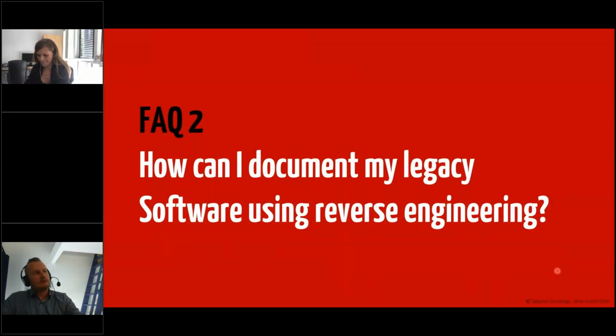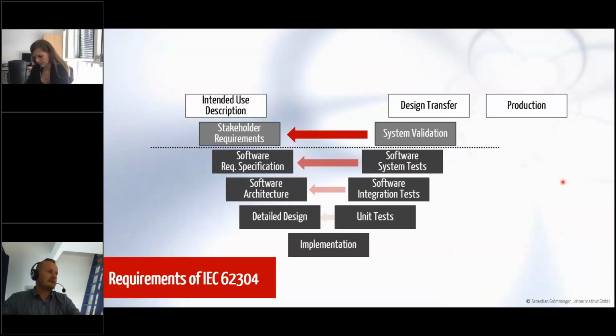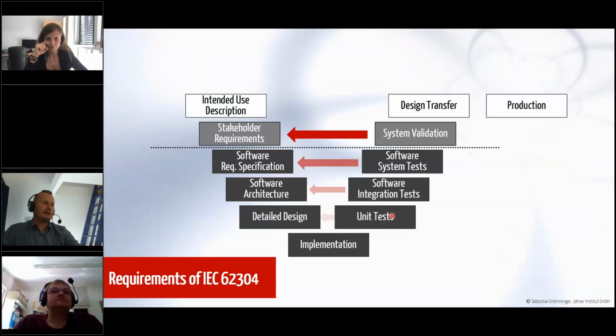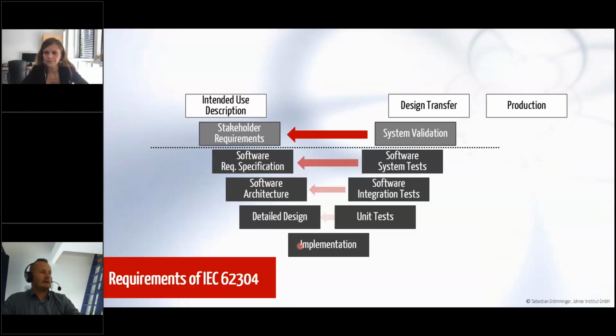The next question was, how can I document legacy software using reverse engineering? In this case, I would use the requirements of the IEC 62304 and the respective V model, and go from your system validation that you have hopefully done for your product already, and from that derive your stakeholder requirements. Hopefully you have done software system tests, and from those system tests you can derive software requirement specifications back. Most software systems will end up there because you won't find integration tests and unit tests. If you find those, you will certainly already have sort of a compliance to IEC 62304. However, if you're there, you can go this way in the normal way. So this would then not be, again, reverse engineering; you should simply engineer your software.